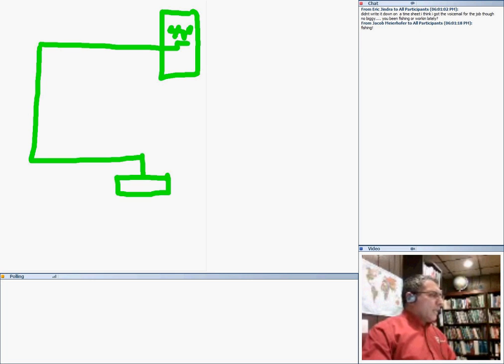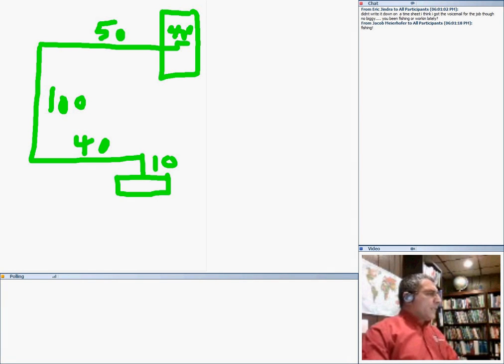Okay, that's just for the heck of it. Now, I might need, and these distances, let's just say this is 50 feet here, and I have 100 feet here, and let's say 40 feet here. So that's a long run, and I have 10 feet down to my panel. So a good application for this, guys, because of exceeding the 360 degrees of bends and all this good stuff, would be if you put a pull box right in here for your conductors. So that's my pull box. Very good application for that.